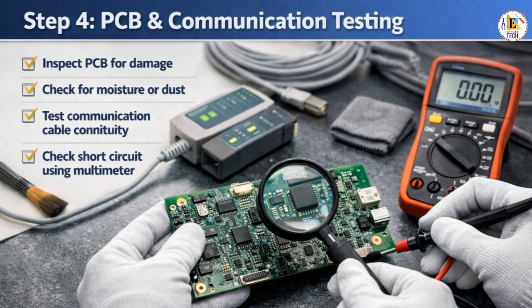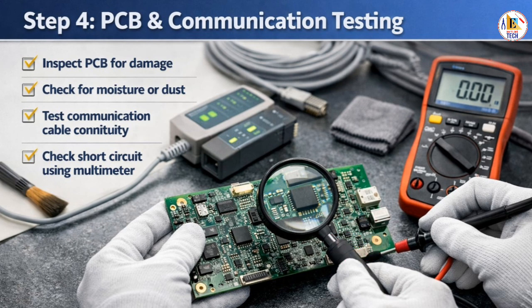Step 4. PCB and communication testing. If the error persists, the next step is to check the PCBs themselves. Inspect each board for dust, moisture, or any visible damage. Then, test the communication cables using a multimeter to check for continuity and ensure there are no short circuits. This step helps you determine whether the problem lies within the wiring or the PCBs. Proper testing at this stage can save time and prevent unnecessary replacements.